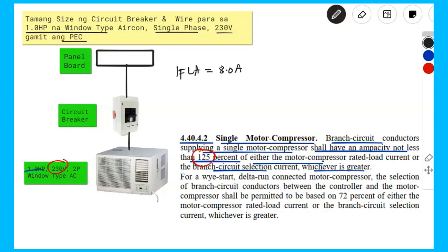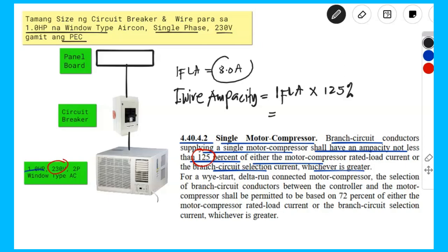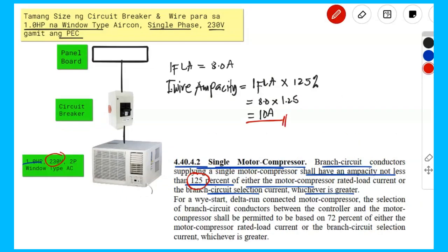So, if i-solve natin yung ampacity ng aircon natin, yung IFL, or we can have that as the current for wire ampacity. That is the full load ampere, and then times the factor of 125%. So yung ampacity natin or full load ampere, that is 8.0, then times 1.25. So yung size ng wire natin, if we calculate, we can have 10 amperes. Okay, so dito tayo mag-reference para sa size ng wire natin, 10 amperes.